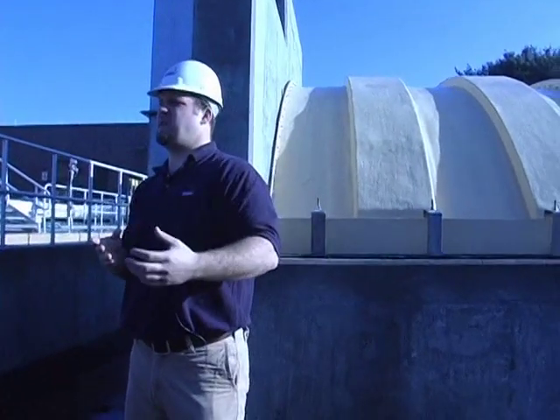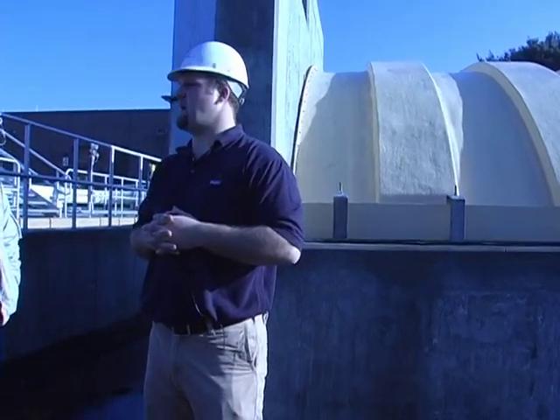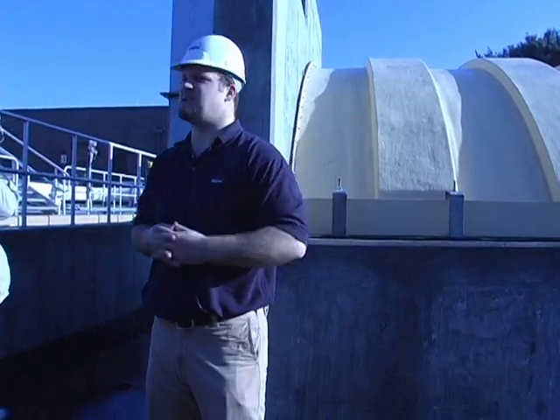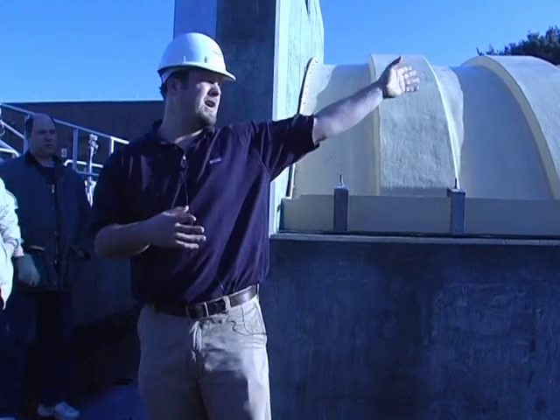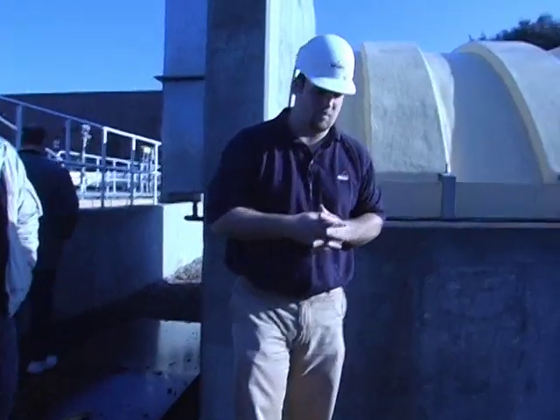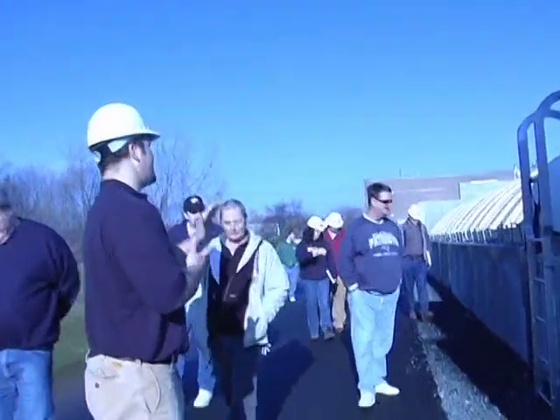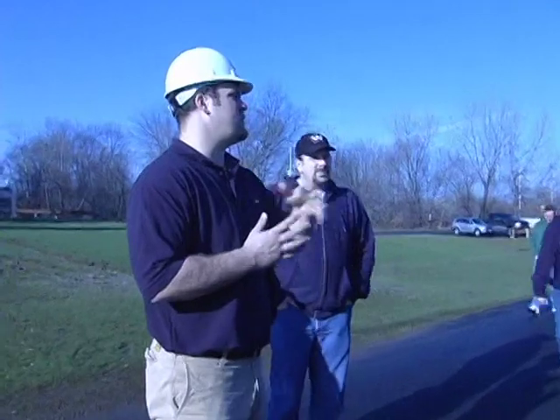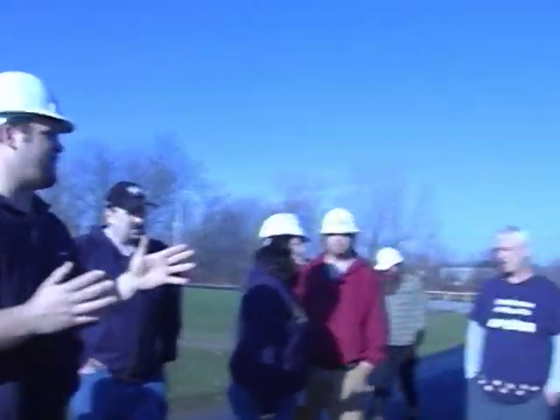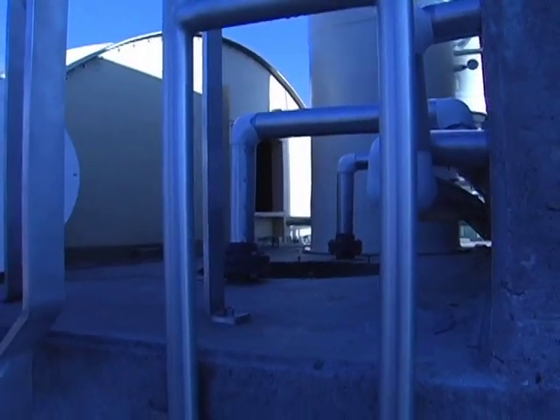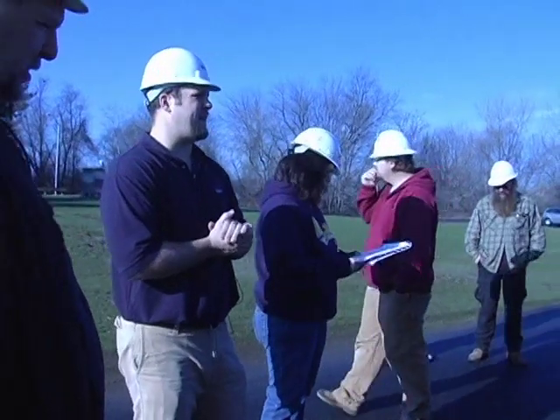Also, if we want to take a walk around the other side real quick, that's where the drain trap cleanouts come up from the biofilter drains and the humidification drains. So that's where that procedure would be taking place, just around the other corner here of the humidification system. For maintenance purposes, if you ever need to do any maintenance on anything in the pre-humidification chamber, you're going to want to shut the airflow off first before you take this manhole cover off. That could be real dangerous, because with that airflow, if that cover's loosened up at all, it could fly off and potentially injure someone. So shut everything down. Yep. Lockout, tagout.